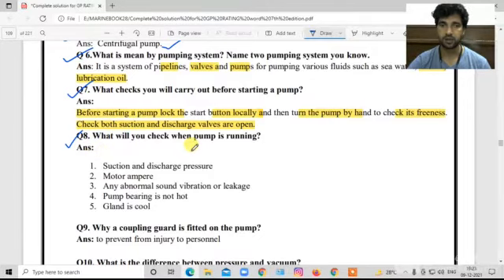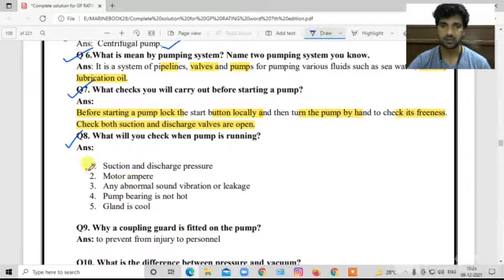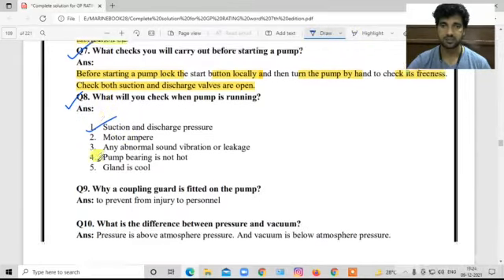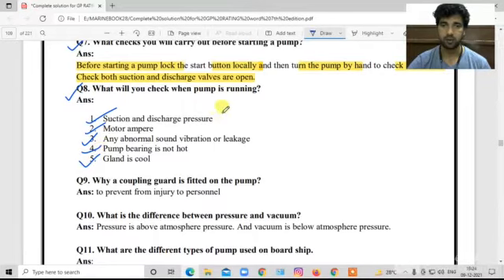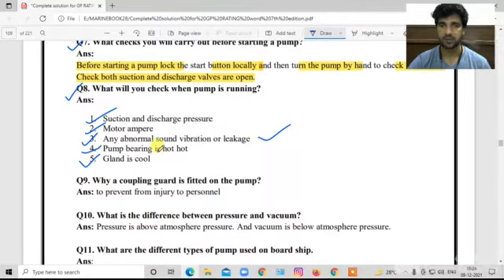What will you check when the pump is running? Check suction and discharge pressure; check motor ampere (MPL); check for any abnormal sound and vibration; check that the pump bearing is not hot; check the gland — that it is properly cooled. The key common points to always remember are: abnormal sound, vibration, and leaks.